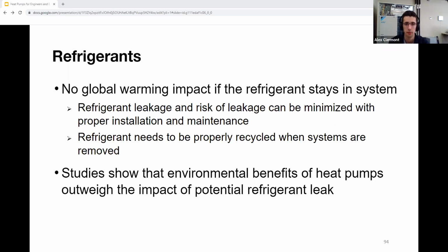Now we're excited about the arrival of R32 as a next generation refrigerant with higher efficiencies, lower GWP, and just overall less of it. But in the meanwhile, R410A systems are safe to install and they go through their life without any issues. We just have to focus on quality installs and keeping the refrigerants inside of them.